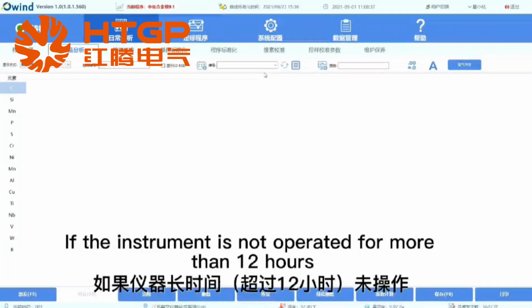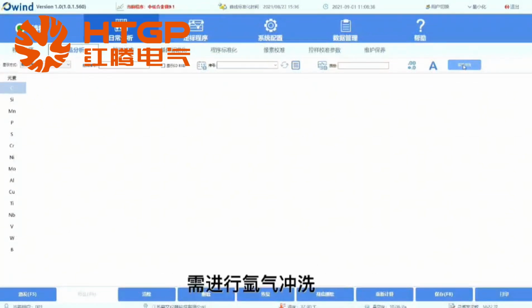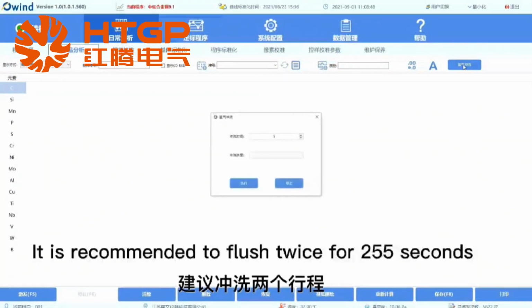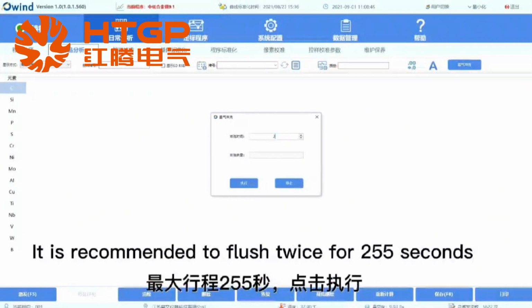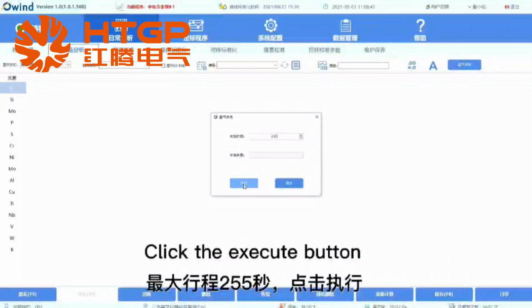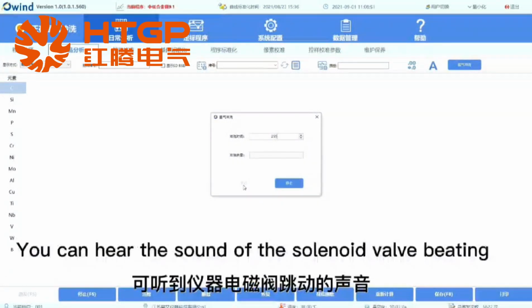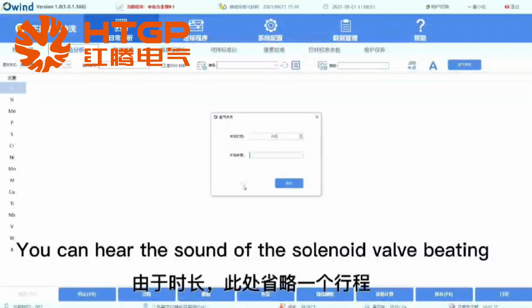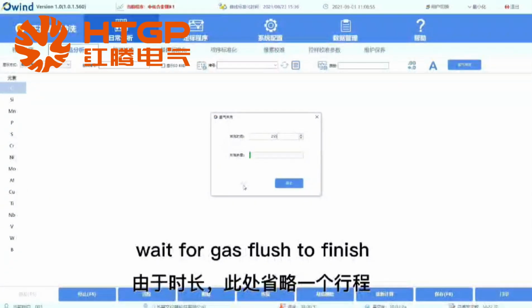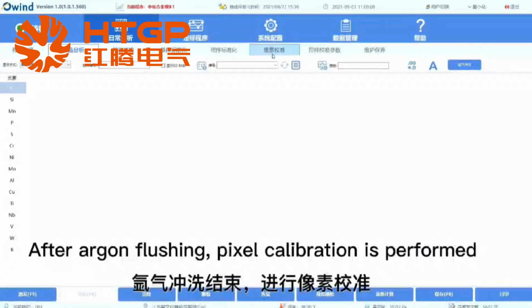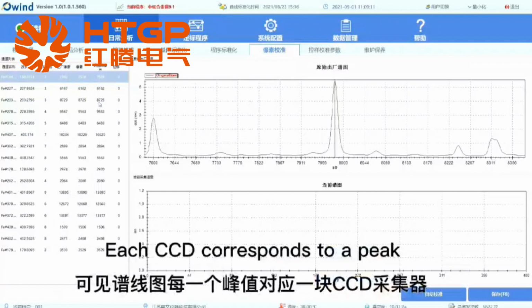If the instrument is not operated for more than 12 hours, argon flushing is required. It is recommended to flush twice for 255 seconds. Click the execute button. You can hear the sound of the solenoid valve beating. Wait for gas flush to finish. After argon flushing, pixel calibration is performed.